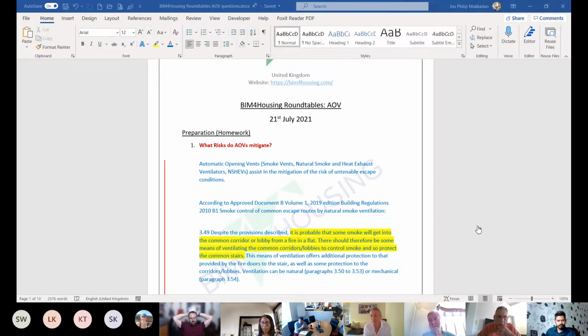And that sofa, or the furniture that was in there, had actually been in there for 18 months. If they had had a fire at that stage, that AOV would have been completely overloaded, and therefore I think there's other issues. It's okay, the AOV and it being fitted in compliance with how it should, but what are the circumstances in which it is not going to be operational? And I don't think they're always taken into consideration.